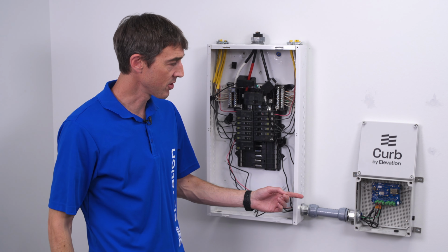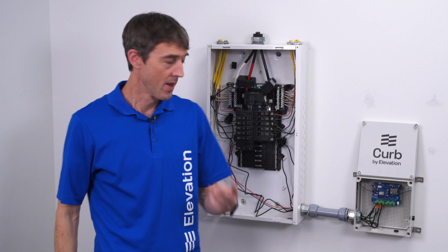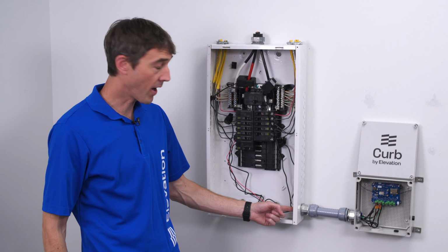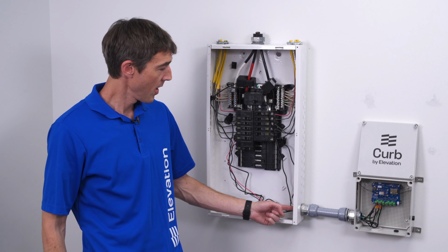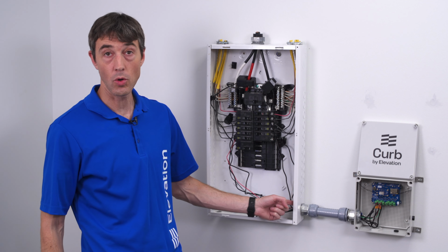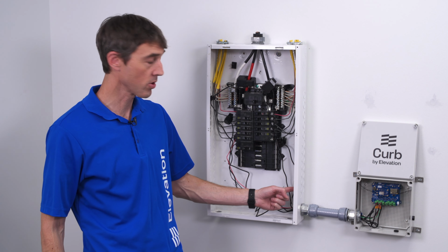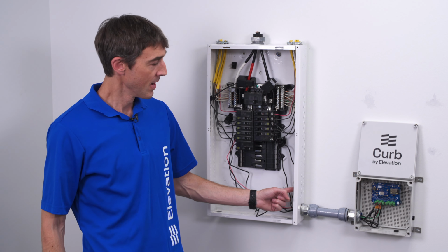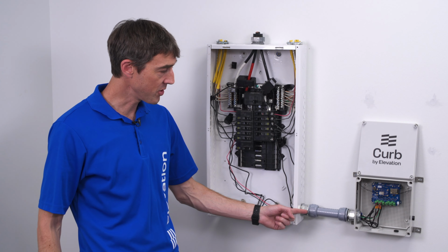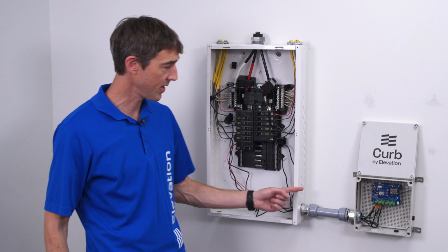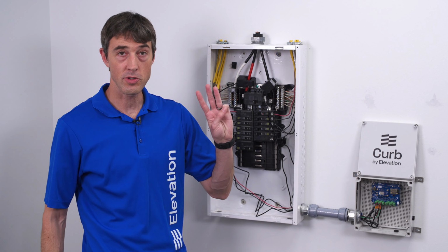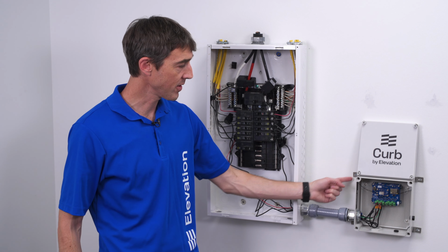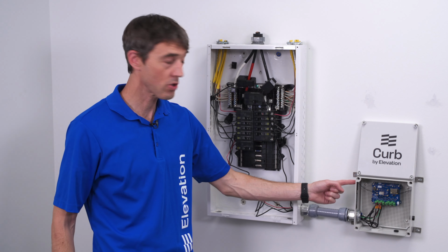The Curb system gets installed in 3 easy steps. First, utilize any knockouts in the existing panel to identify holes, or use the hole saw to add an additional hole to the electrical panel. The second step is to run the conduit across from the Curb device into the electrical panel. And then the third step is simply mounting the Curb device on the wall. And ensure to use a level to make sure it's level.